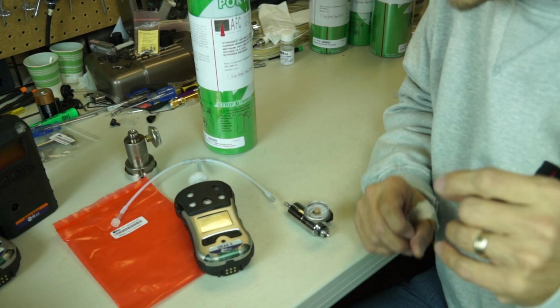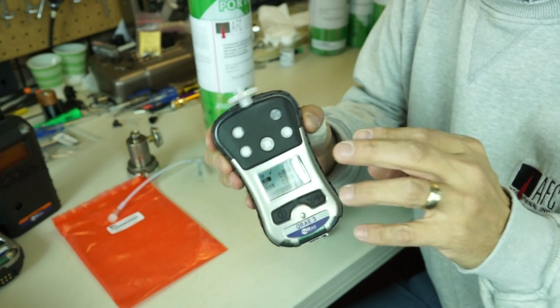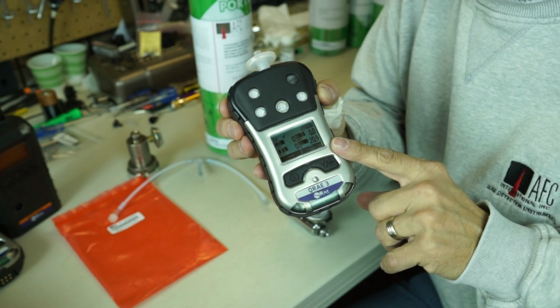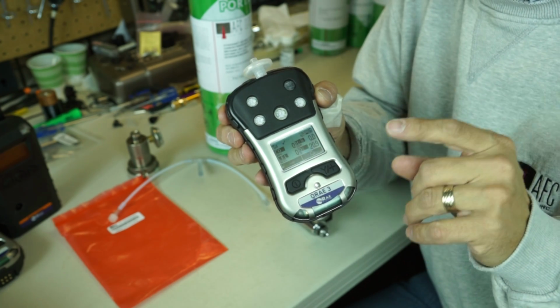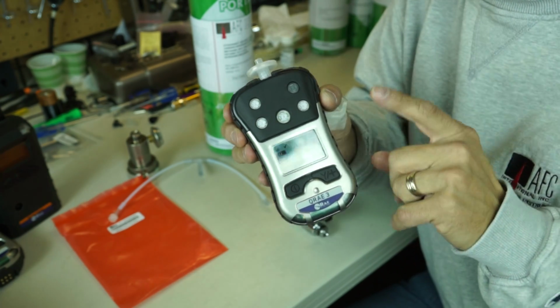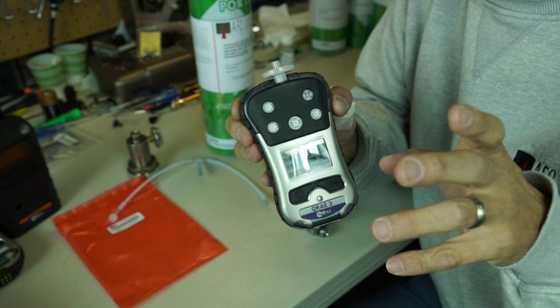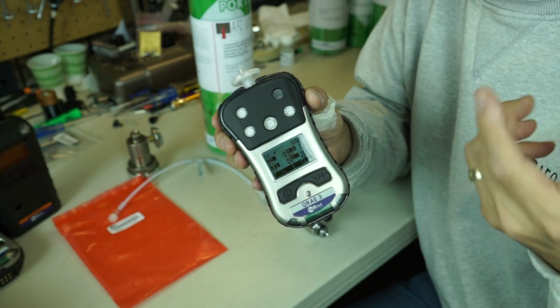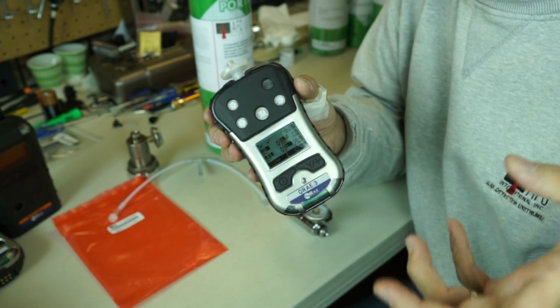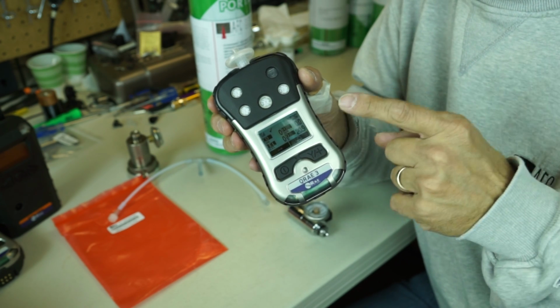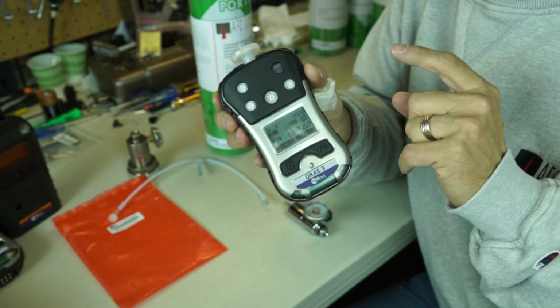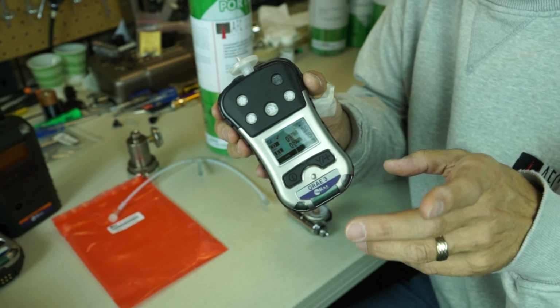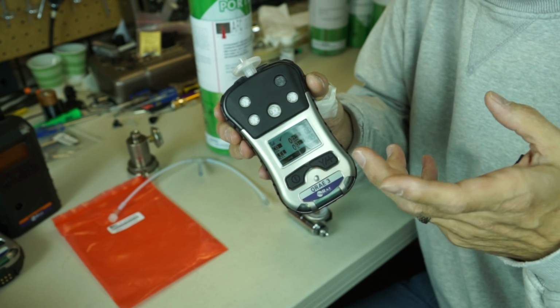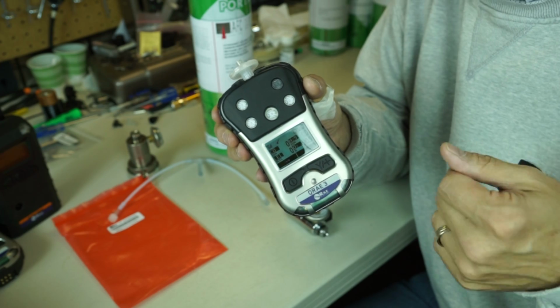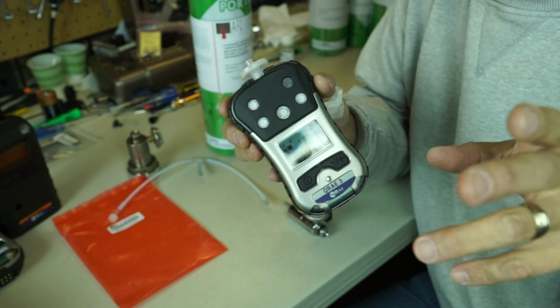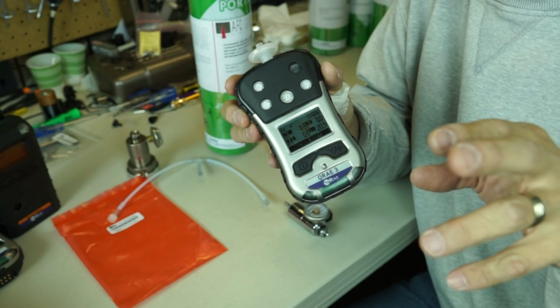Now, the QRae 3 that I have today is an internal pumped unit. They do make it in diffusion, and I can go through that in another video. But for pumped instruments, and you've heard me talk about this for years, AFC always includes a T when we do calibrations. Whenever you have a pumped instrument, and especially this QRae 3, because they've actually given you a T when you purchase the instrument to be used for calibration, I wanted to show you how to use that T and how to calibrate a QRae 3.